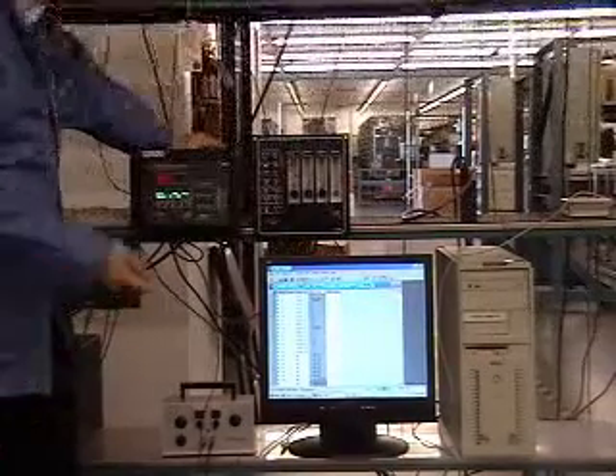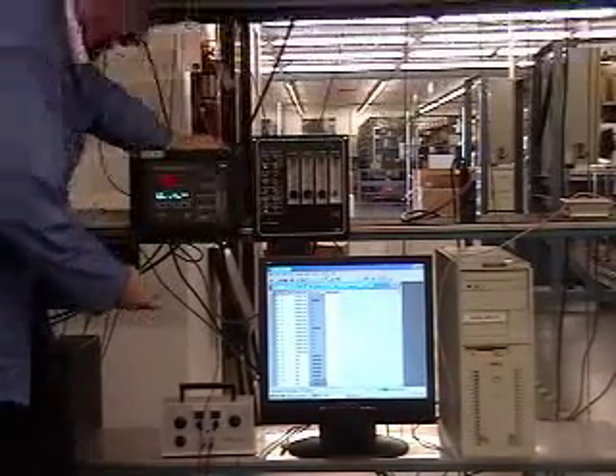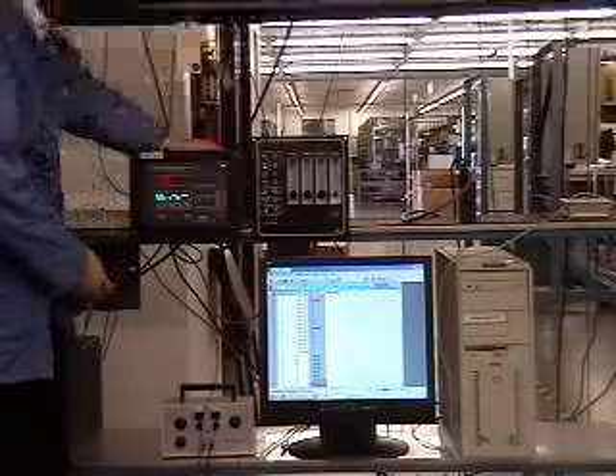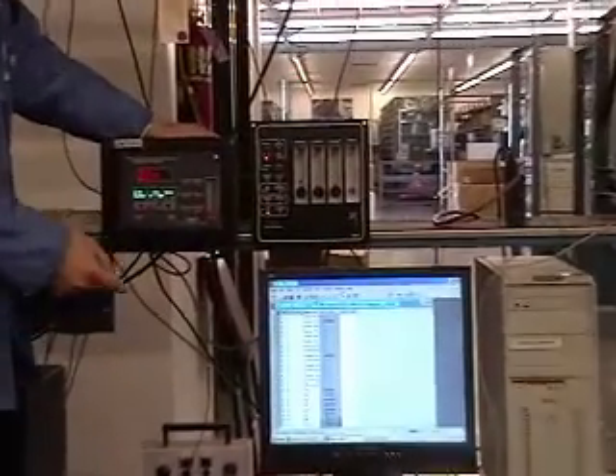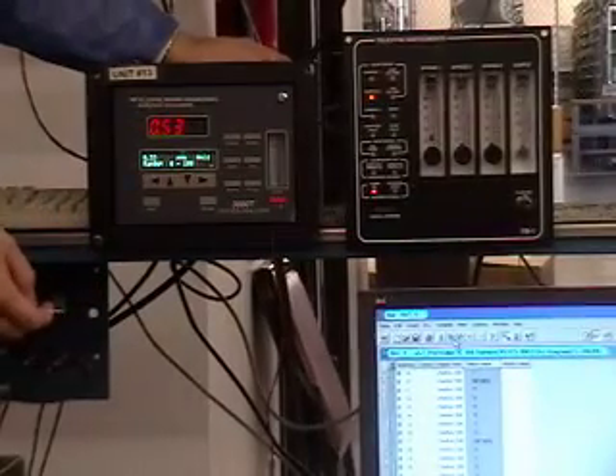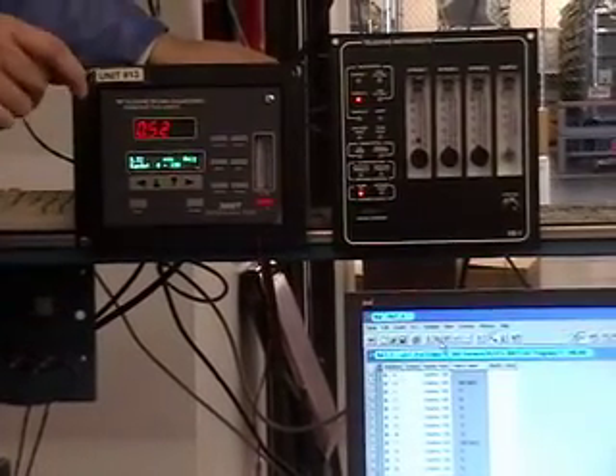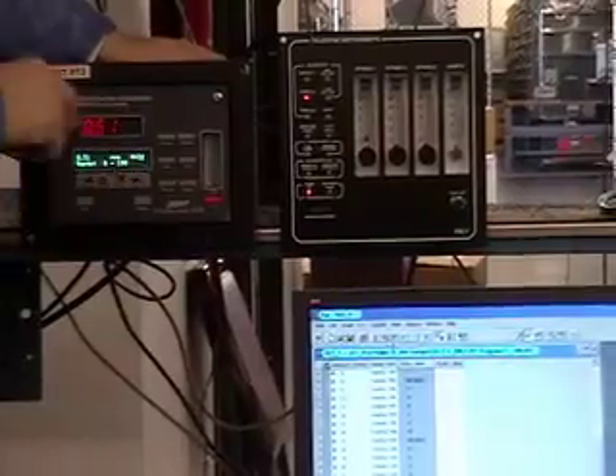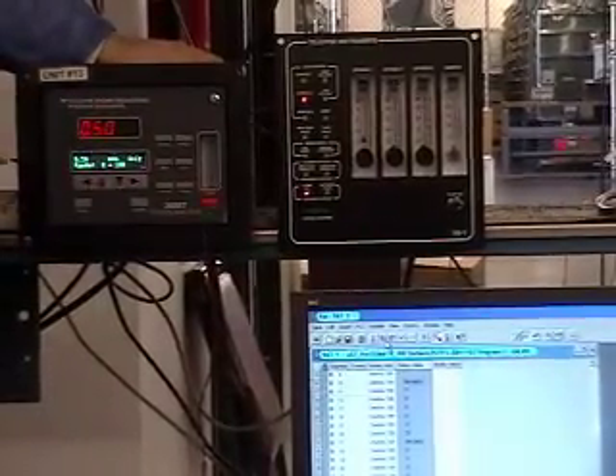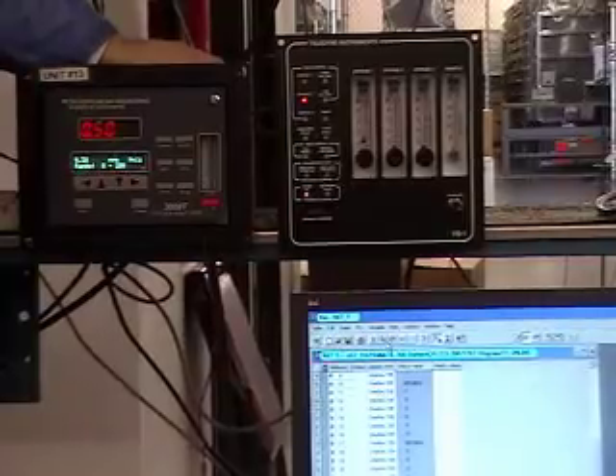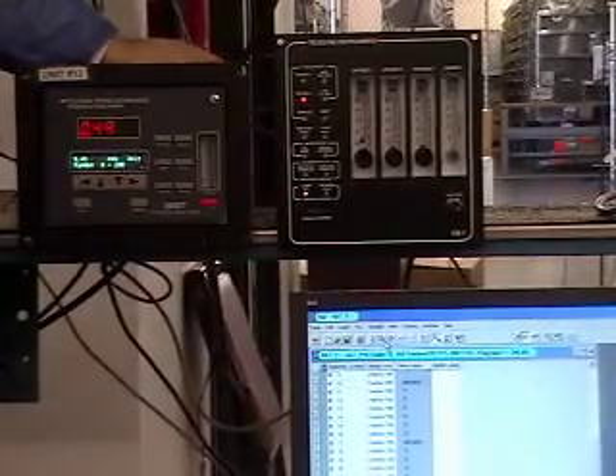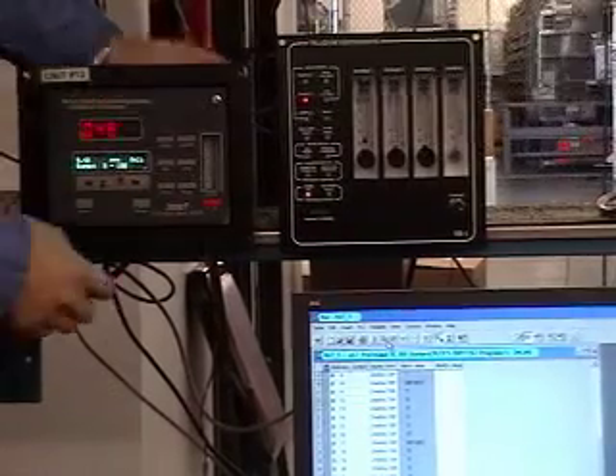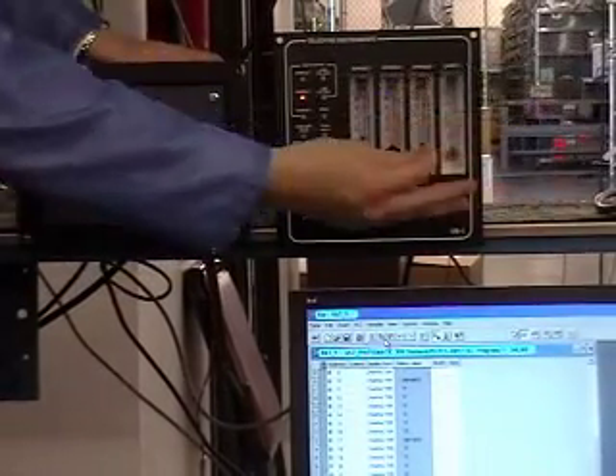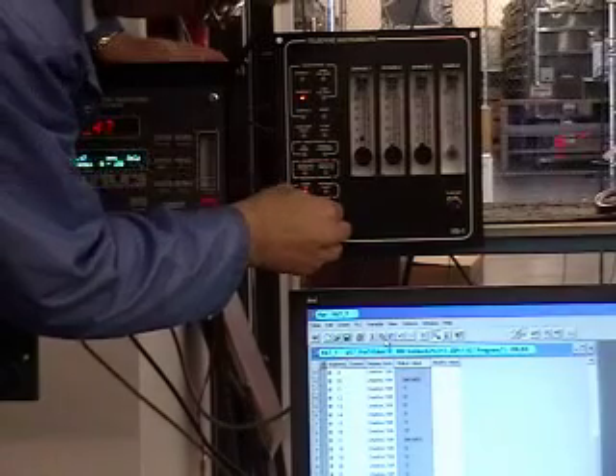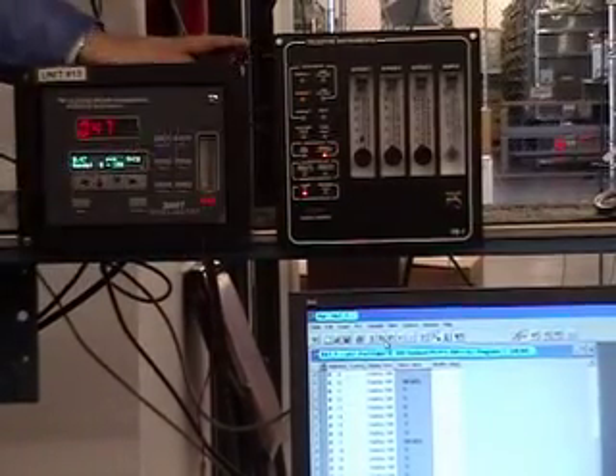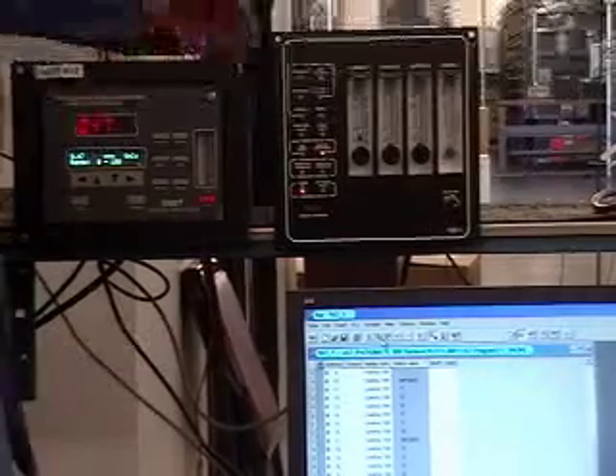But what I'm going to do, this analyzer has RS-232 output, and it has 4 to 20 milliamp output as well. So I'm going to disconnect the RS-232 and connect the 4 to 20 milliamp. And like I was saying, there are analog terminals on the back of the BB1 where you can connect 4 to 20 milliamp. The software knows when to do the switch if you do the sequence properly. The sequence is put it on the manual override. So you move the rightmost switch, position 8, up, manual override light comes on. So now it is in manual override.